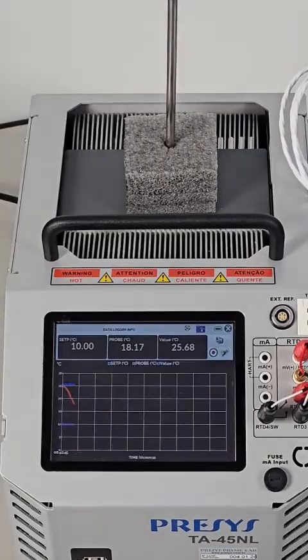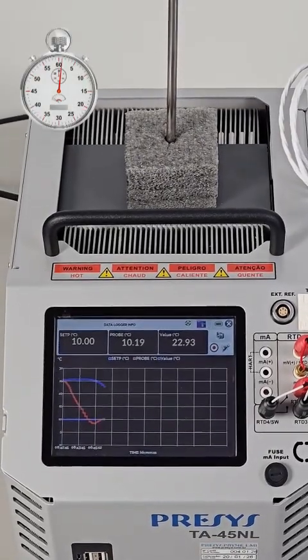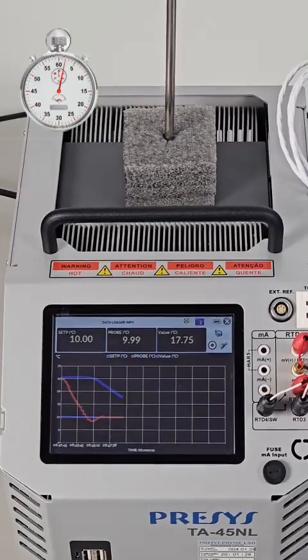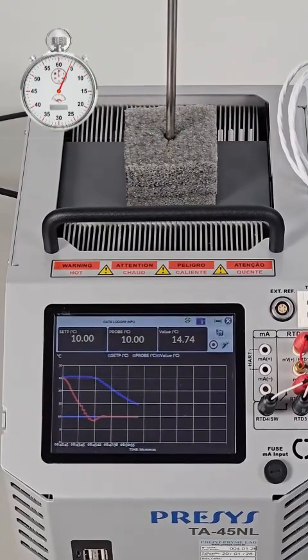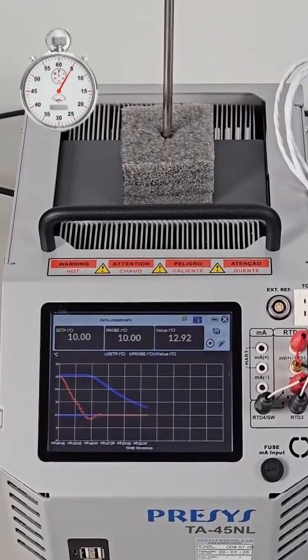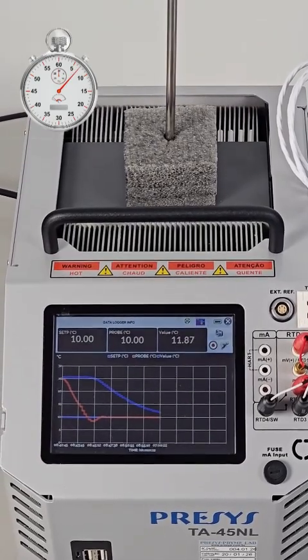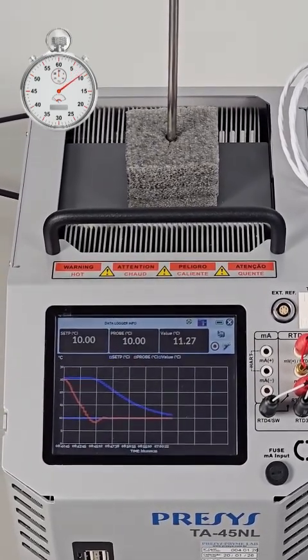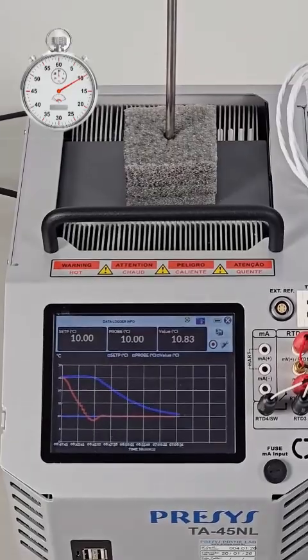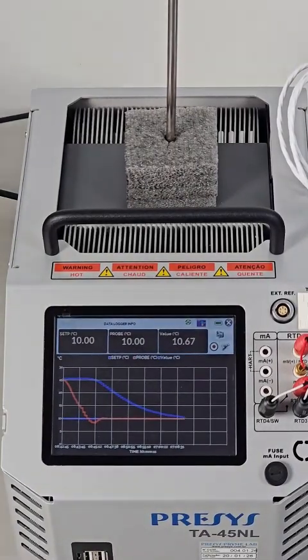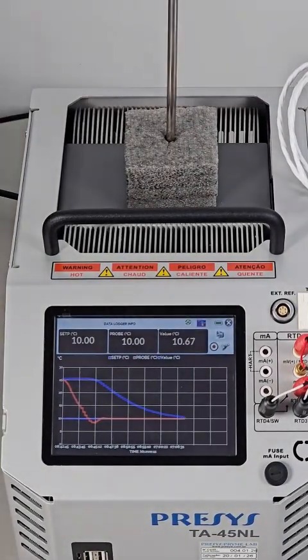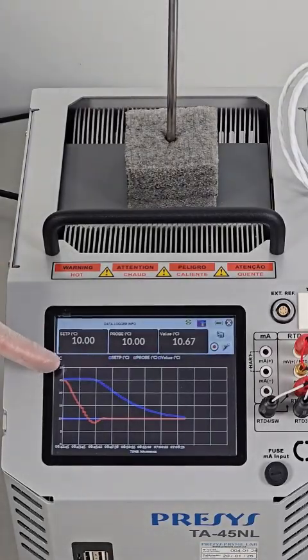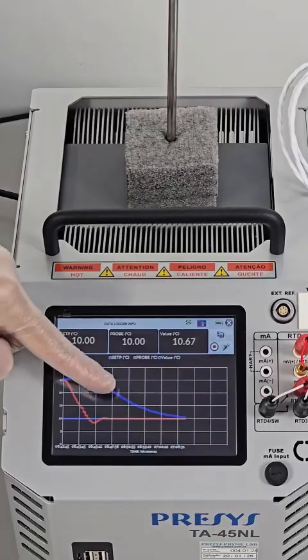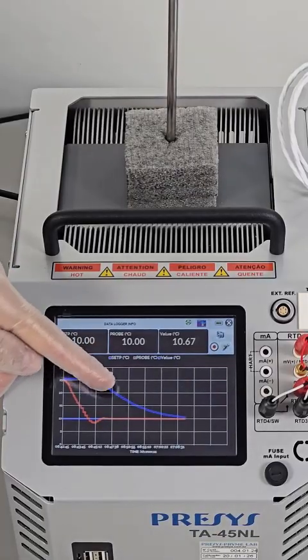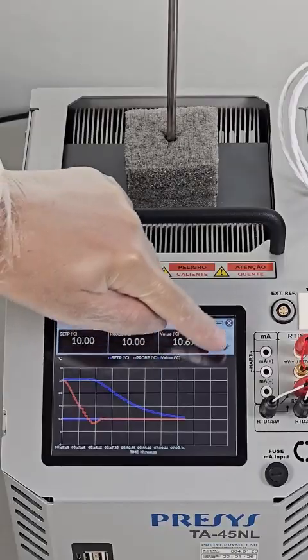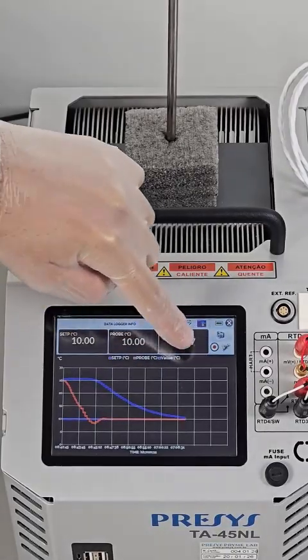The fast response red curve represents the temperature of the block sensor, due to the low thermal inertia of the metal. The slow response blue curve represents the temperature inside the cell, due to the high thermal capacity of the water. Note the characteristic delay between the two curves. While the block has already stabilized at 10 degrees Celsius, the cell is still undergoing thermal equalization. This is precisely why the cell temperature must be monitored instead of relying solely on the bath reading.